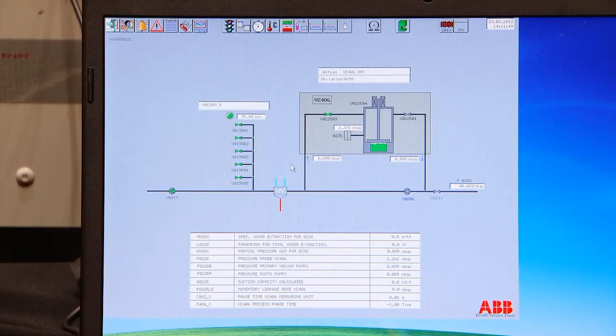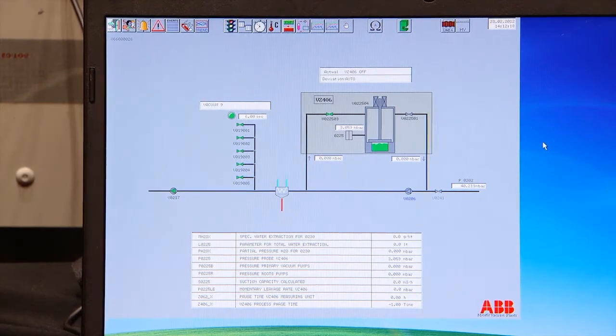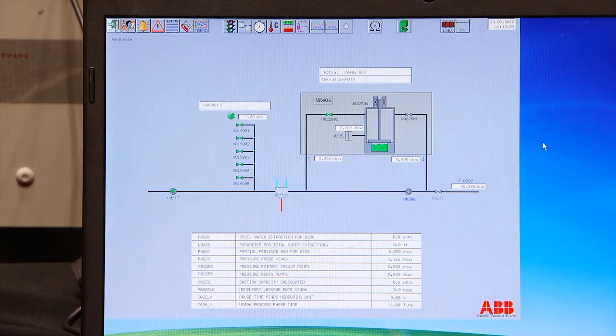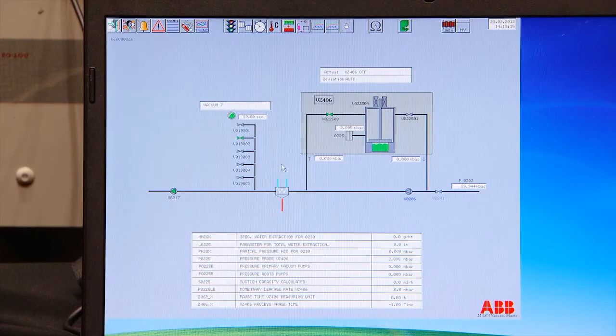The VZ406 is not symmetrical. It has a plus and minus. It has a transformer side and it has a vacuum side. The whole theory behind this is to measure the end vacuum for each leakage level. What is the best vacuum we can reach for each predefined leakage? Inside the VZ406 there are 2 valves, one on each side of the measuring chamber, and we're only using one of the valves to expose the pressure sensor. In the first stage we're using one valve, in the second stage another valve, in the third stage a combination, and so on.